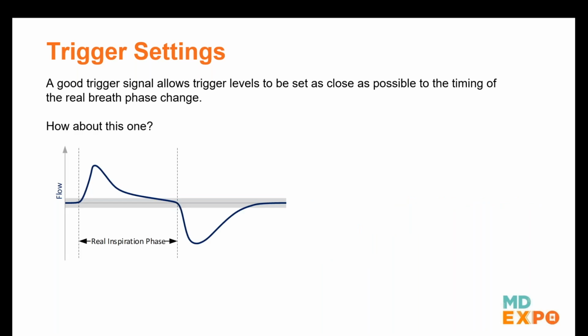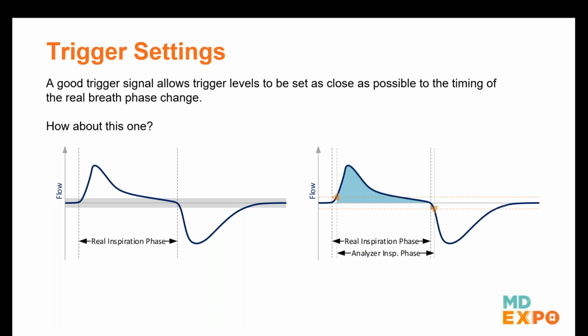So let's have a look at the second example. How about this one? Looks a little bit better, right? Because here we have a positive flow through the flow channel in the inspiratory phase and then a negative flow during the exhalation phase. At both real breath transitions, we have some kind of movement in our signal, which is good, and we can set our trigger settings on that. So here we could set the start trigger to a positive flow on a rising edge, and then the end trigger at a negative flow on a falling edge. That would allow us to quite accurately capture the inspiratory and expiratory phase.